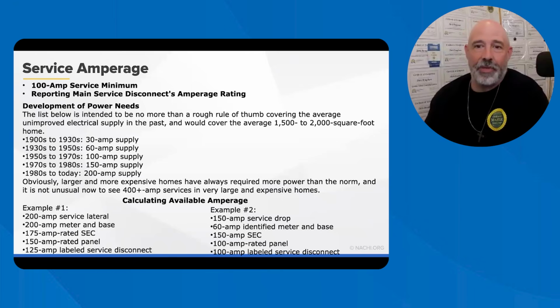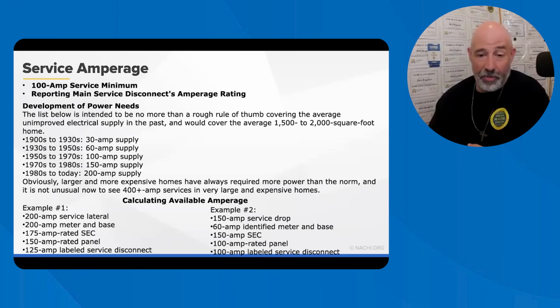In many cases, the listed information about a home may not be correct regarding the service amperage because brokers or owners rely solely on the size of the main breaker or fuse. Many people are also under the mistaken impression that the total available service amperage is the total of the individual breakers or fuses in the service panel. One way for a home inspector to help communicate available amperage is to determine the ampacity of the lowest rated, or the weakest link, in the following components: the service supply, the electrical meter and socket, the service entrance conductor, the service disconnect, and the distribution panel.